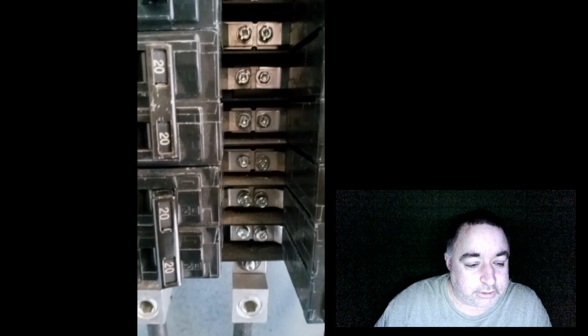So I'm guessing right off the bat that this is loose. I had power on all 3 at the outlet, but when you apply power to the machine and draw any amperage, these connections obviously aren't going to be any good. You could still have voltage there when you're not drawing amperage, but as soon as you put a charge on it...